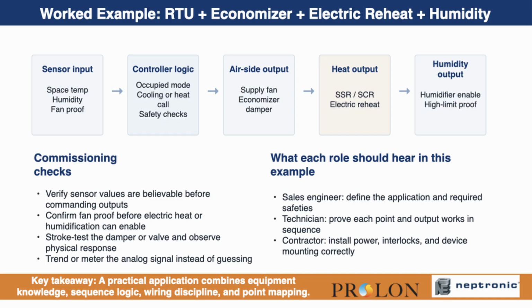Those inputs tell the controller whether the space is too warm, too cold, too humid, or operating without proven airflow. The controller logic then decides whether the unit is in occupied mode, whether cooling is needed, whether economizer cooling is available, whether electric reheat is needed to maintain discharge or space conditions, and whether humidity control should be enabled. On the airside outputs, the controller may enable the supply fan and modulate the outdoor air or economizer damper. On the heat output side, it may command staged or modulating electric reheat through a relay, SSR, or SCR, depending on the design. On the humidity output side, it may enable a humidifier, provided that the required safeties such as airflow proof and high limit protection are satisfied.